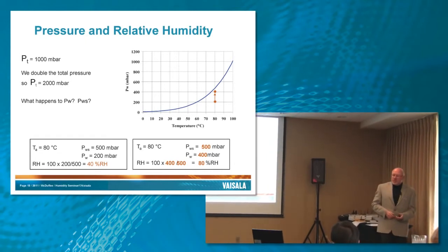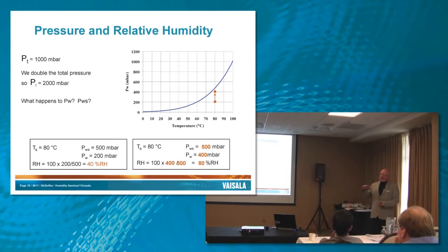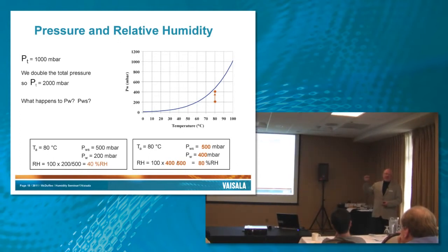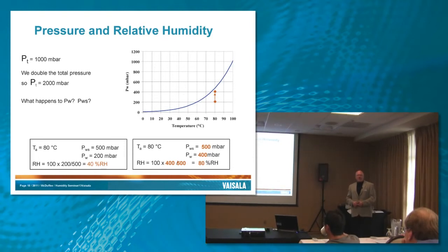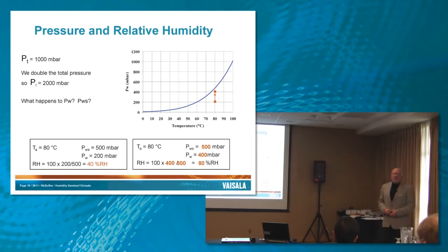The compressor plant manager should know that if I increase my pressure from 80 to 100, that 20 psi difference is going to move me closer to saturation. Depending on how dry the air is to begin with, you may or may not get water in the air lines from that change. But you need to know that increasing pressure approaches saturation.